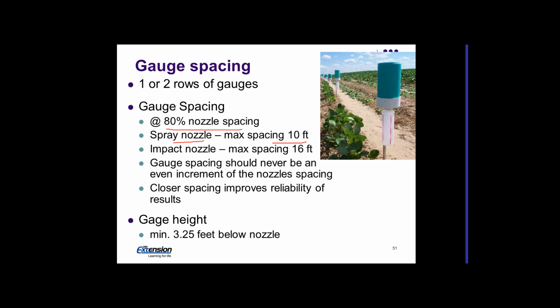Now, if it happens to be at an even increment, so say we had impact sprinklers that were at 32-foot spacing, which isn't odd for a high-pressure system, and the maximum spacing for the impact is 16, that's an even increment of 32. So we want to change that spacing. Typically I would use 80% of that, so about 12-foot spacing for that system.